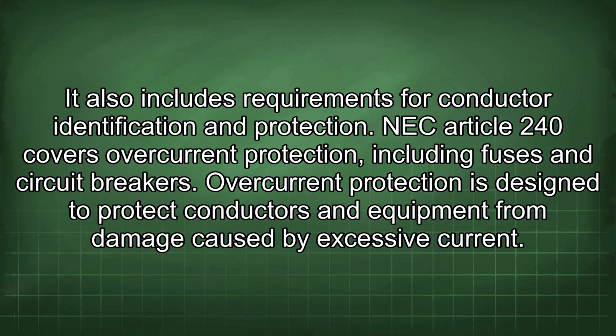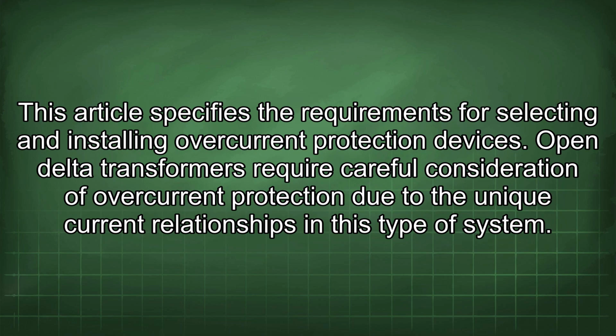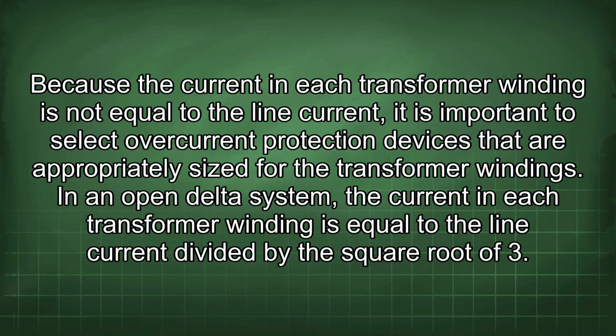NEC Article 240 covers overcurrent protection, including fuses and circuit breakers. Overcurrent protection is designed to protect conductors and equipment from damage caused by excessive current. This article specifies the requirements for selecting and installing overcurrent protection devices. Open delta transformers require careful consideration of overcurrent protection due to the unique current relationships in this type of system. Because the current in each transformer winding is not equal to the line current, it is important to select overcurrent protection devices that are appropriately sized for the transformer windings.